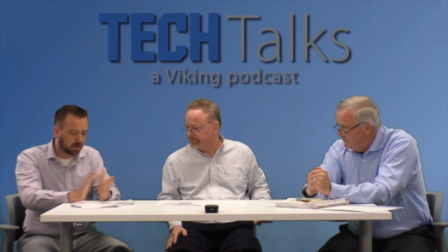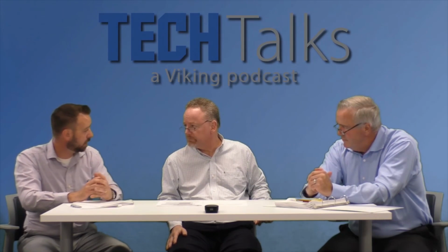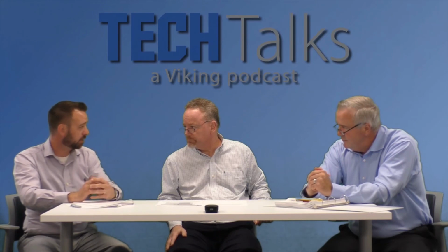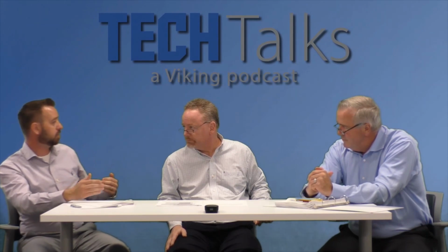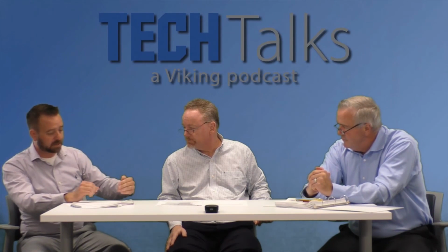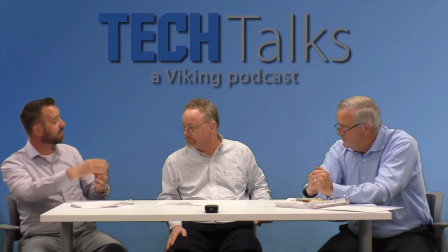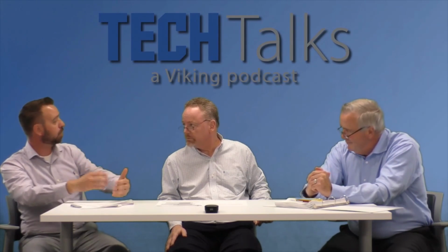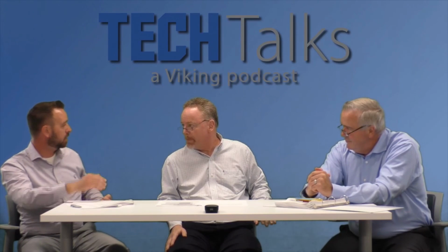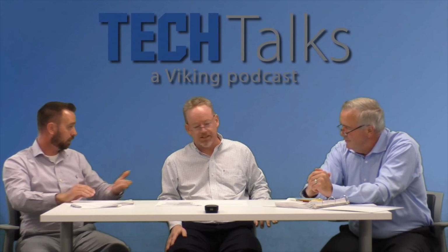Yep, great. Sean, any final thoughts from you? Just going back to the tables that James created, one thing I would want to point out is when you're looking at the number of sprinklers you calculate per branch line, anytime you get above 0.49, that's when you round up. So anytime 0.49 or less, you can round down. Anytime you exceed the 0.49, that's how you're rounding up.